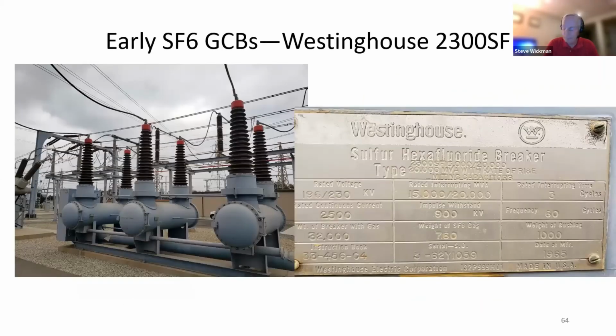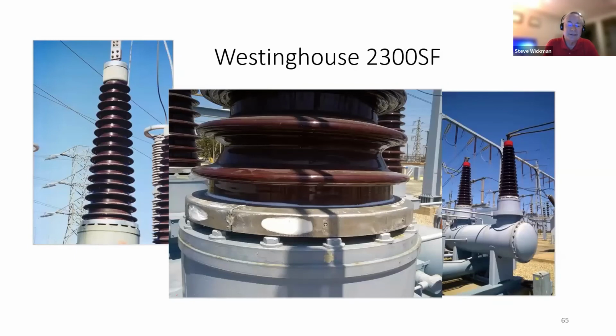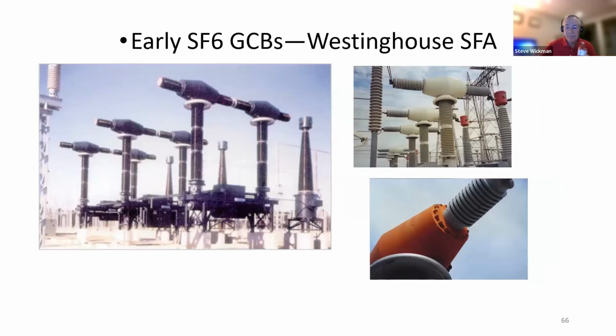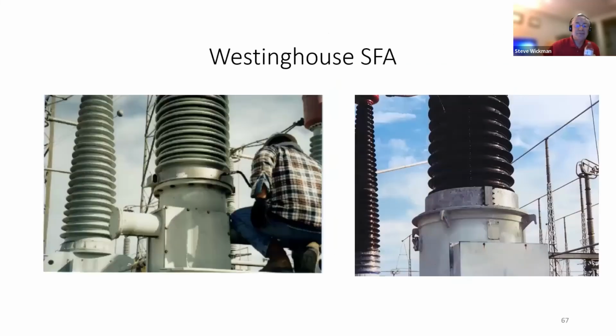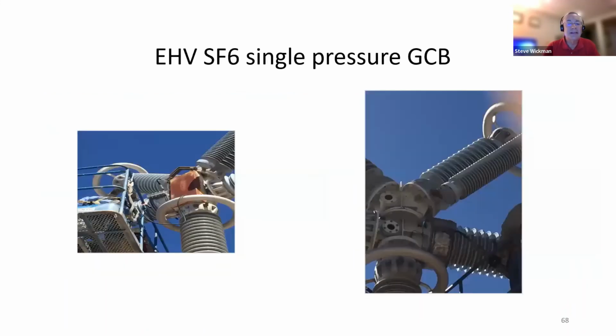And another one, these are even older. This is a 1965 vintage, I believe, Westinghouse SF breaker that it just amazes me the number of these that are still in service around the country. We have worked on putting clamps on bushings on these, both on the West Coast and over in Pennsylvania. So there's a number of these old guys that are still successfully in service. Again, the Westinghouse SFA, the gas-filled columns on these have a tremendous propensity to develop leaks, and we've designed clamps to go around the bases on those to address the gas leaks.